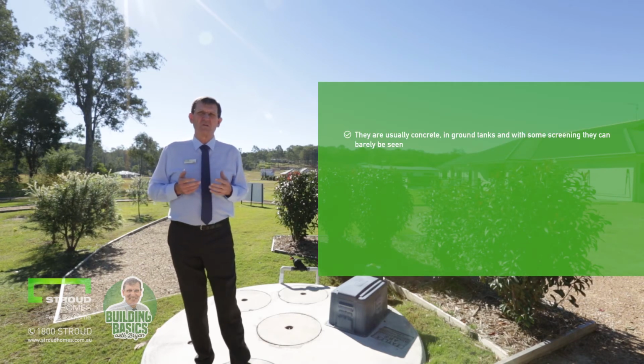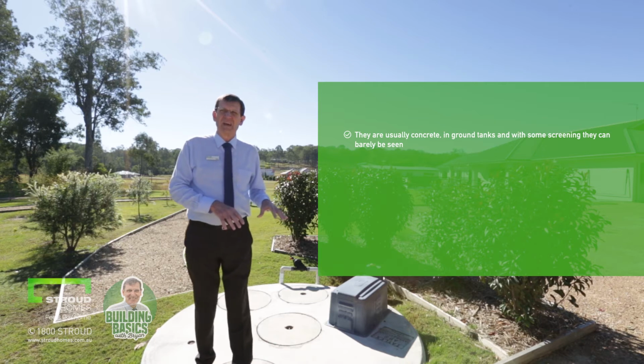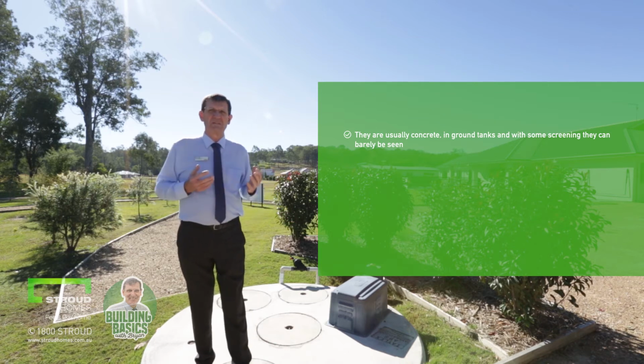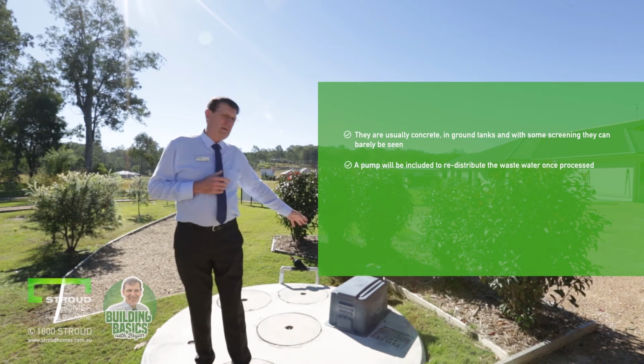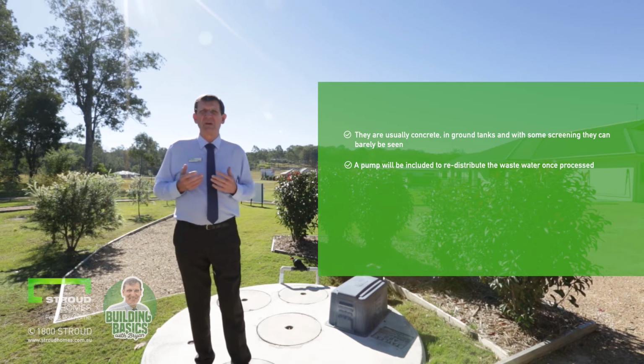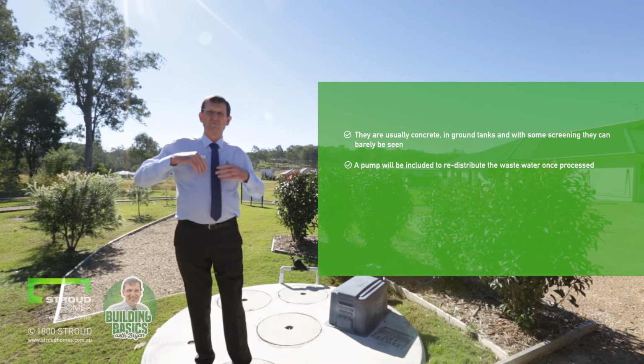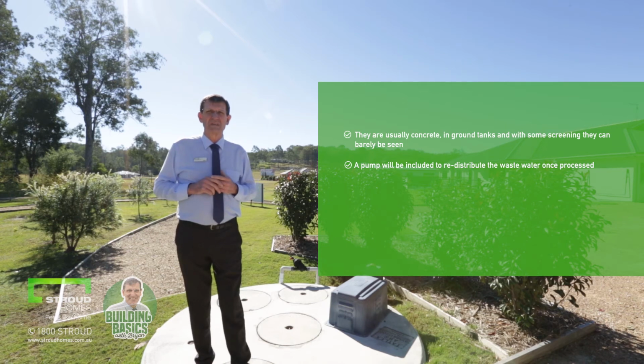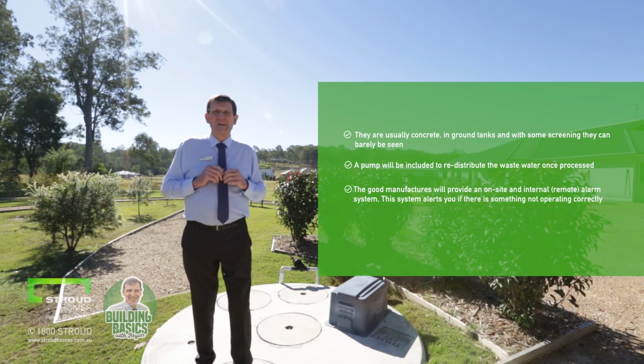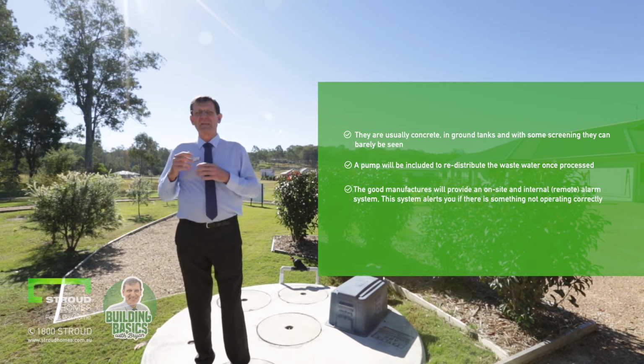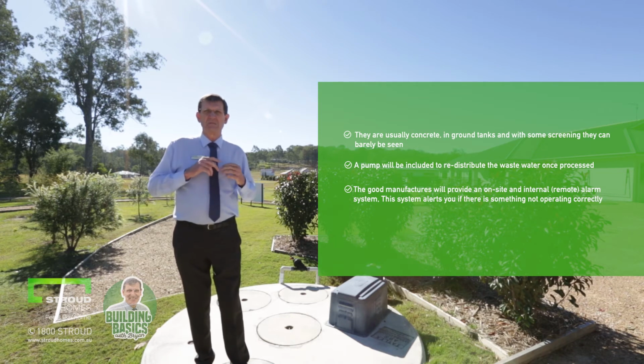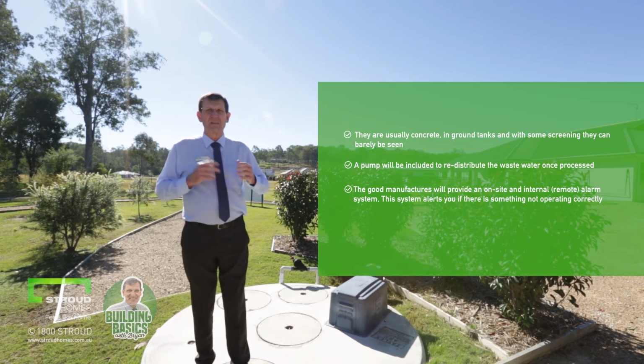They are usually concrete, in-ground tanks with some screening. They can barely be seen. A pump will be located just to my left here that helps redistribute the water once processed. A good manufacturer will provide on-site and internal remote alarm systems so that if something goes wrong, it comes to your attention immediately. They must be submitted to council for approval.